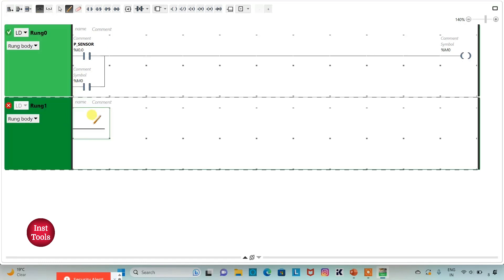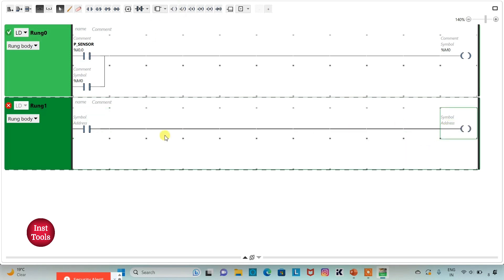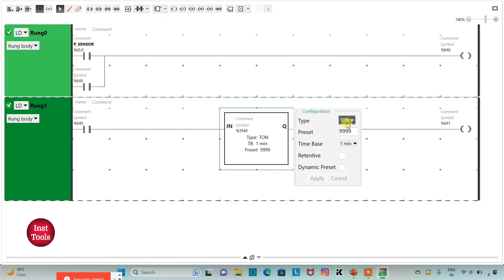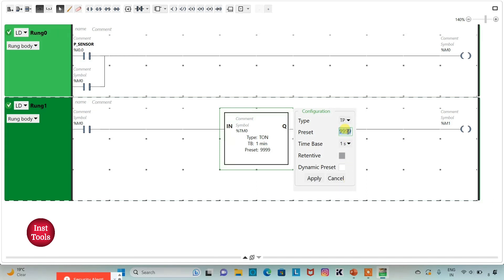I will add a new rung. I will insert a normally open contact and then a coil. I will assign address M0 to the normally open contact and address M1 to the coil. For M1, I will use a timer of type TP. I will change the type to TP and set the preset value to 10 seconds, then click Apply.